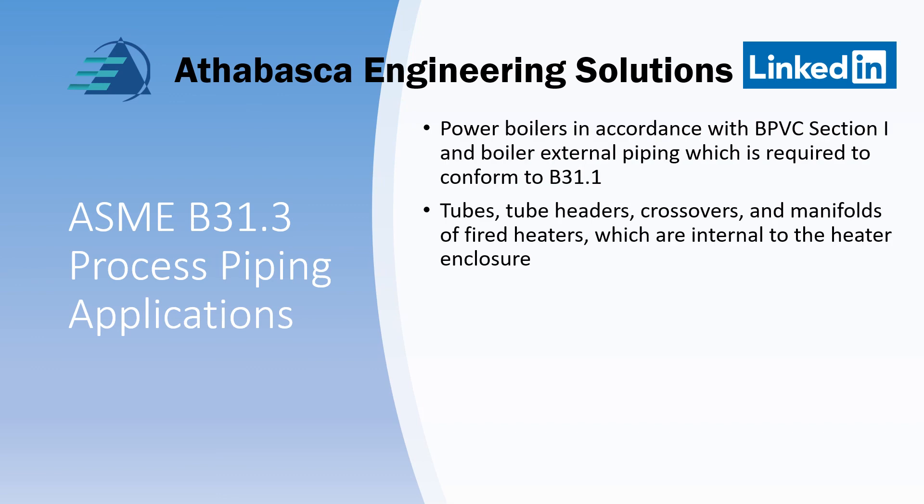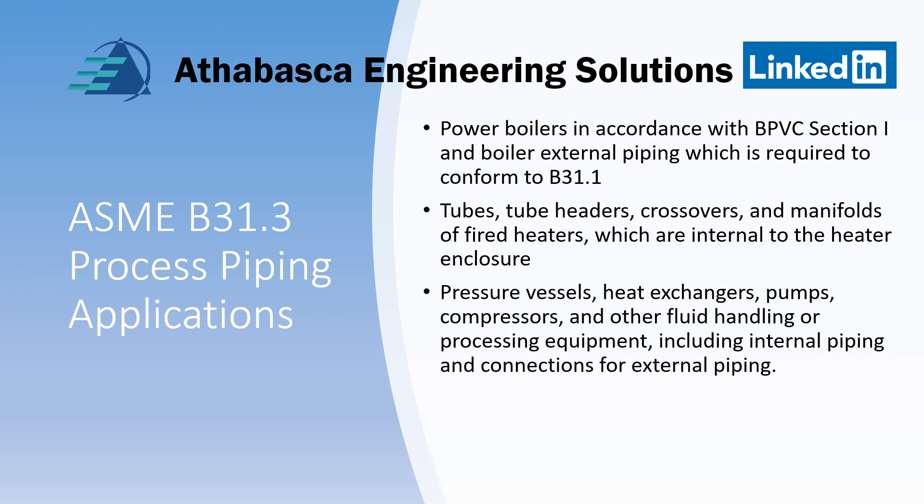Power boilers in accordance with the Boiler Pressure Vessel Code Section 1, and their external piping, fall under B31.1 not B31.3. Also excluded are tubes, tube headers, crossovers, manifolds, or fired heaters which are internal to the heater enclosure, and pressure vessels — that's basically equipment.